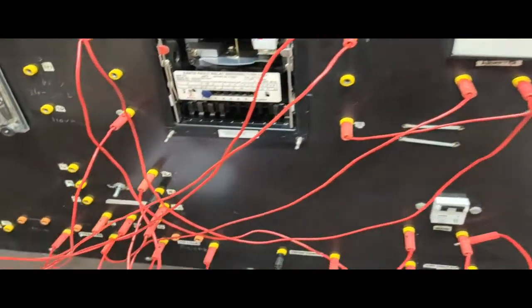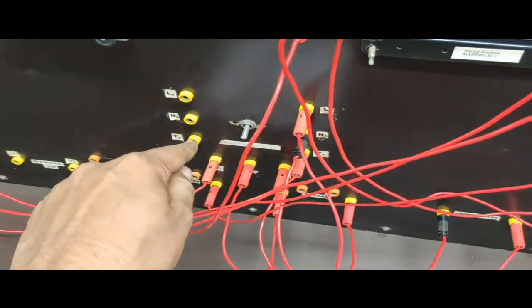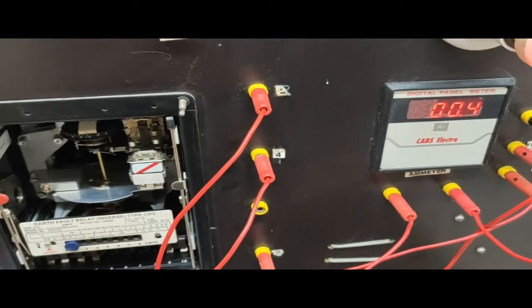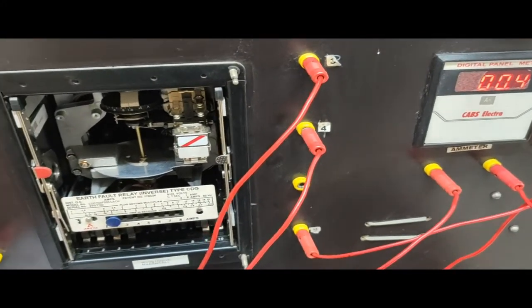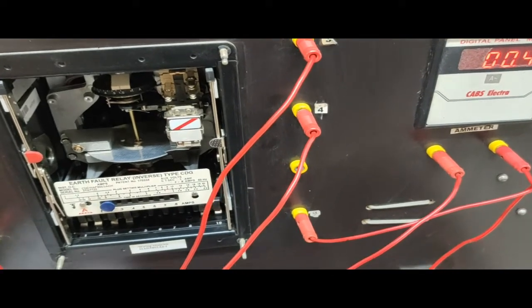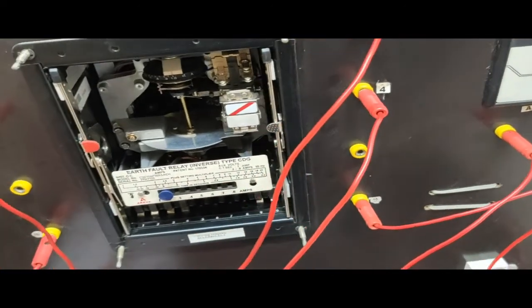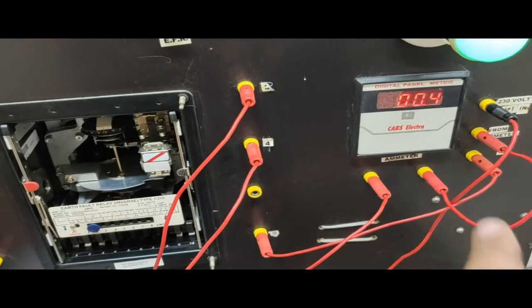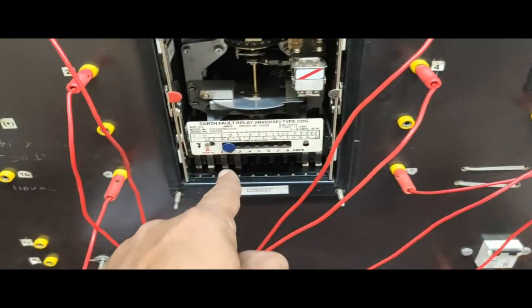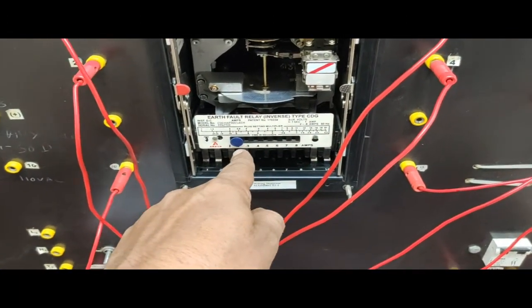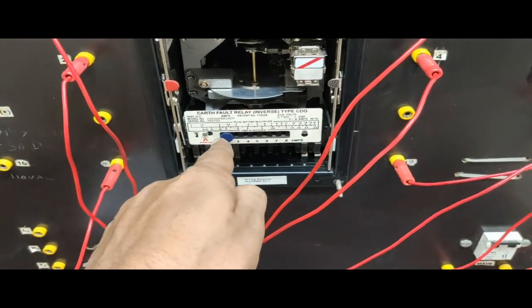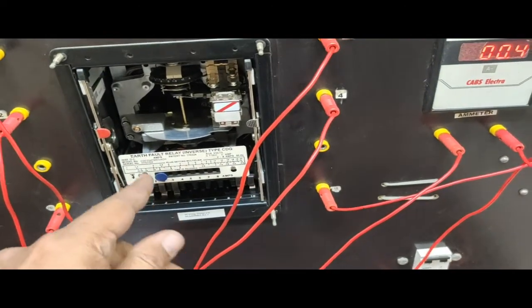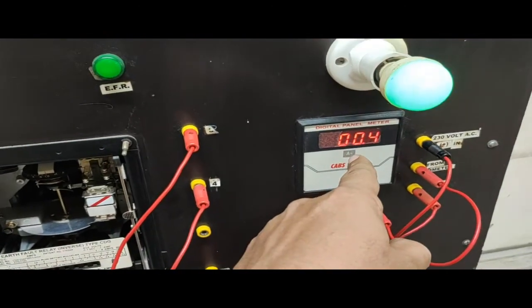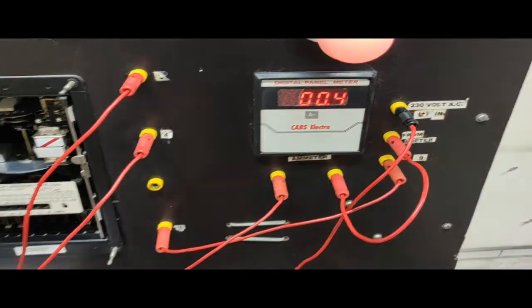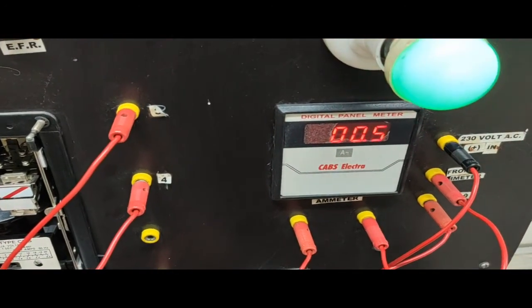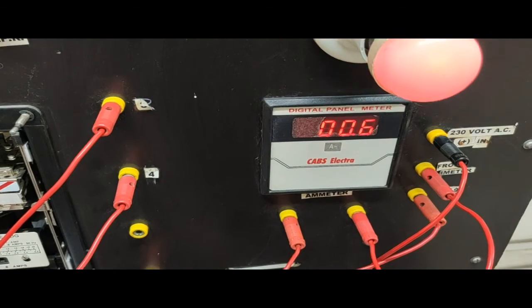So the procedure is that first you need to put the selector switch in the downward position, then you need to give the required amount of current so that the plug setting multiplier will be 3. So what is the plug setting multiplier? Plug setting multiplier is the relay current divided by the plug setting. Now the plug setting is 0.2. So that means to make the plug setting multiplier 3, we need to give relay current 0.6. So first I am giving relay current 0.6.